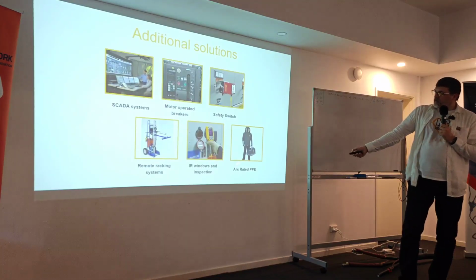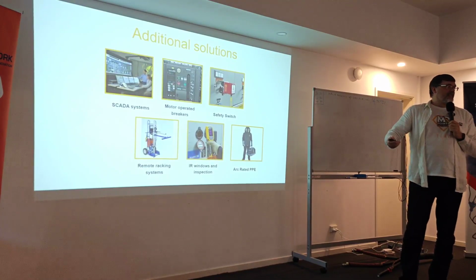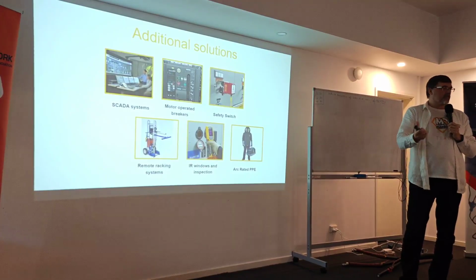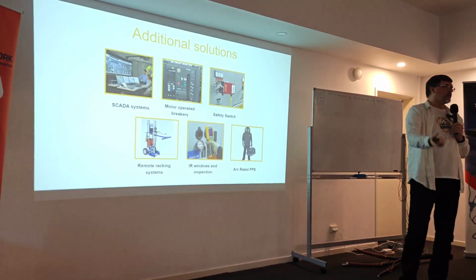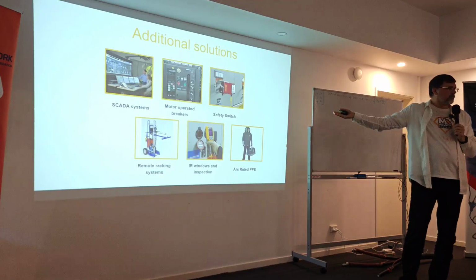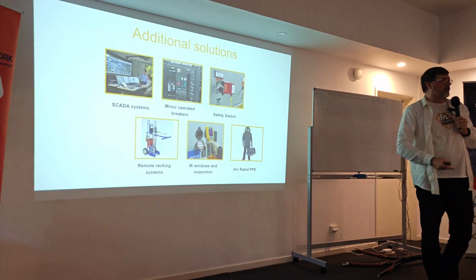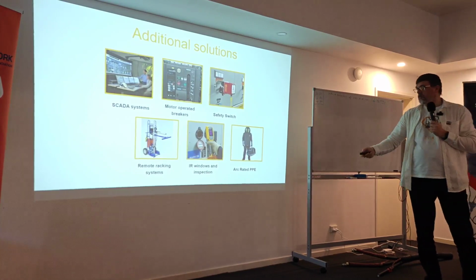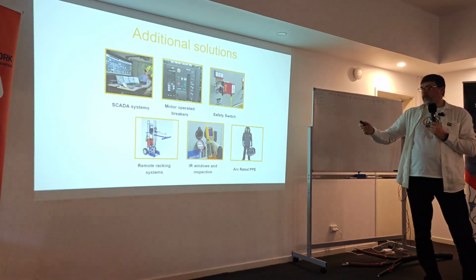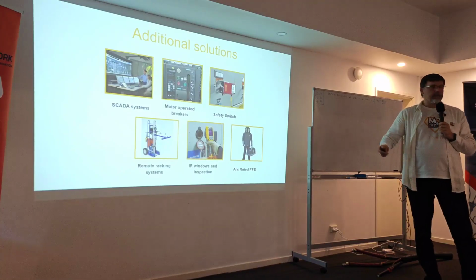There are some other things, you can see there's a lot of things to handle this, yeah? If you have a SCADA system and motor operated breakers, you can have remote operation by default, which is almost 100% of how medium voltage networks work, yeah? We don't operate standing in front of the breaker, we just do it remotely or locally sometimes, but locally doesn't mean standing in front of the breaker.